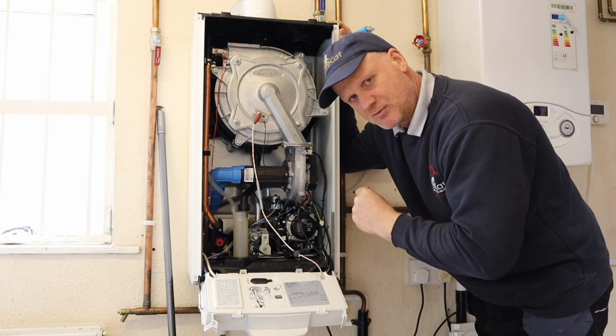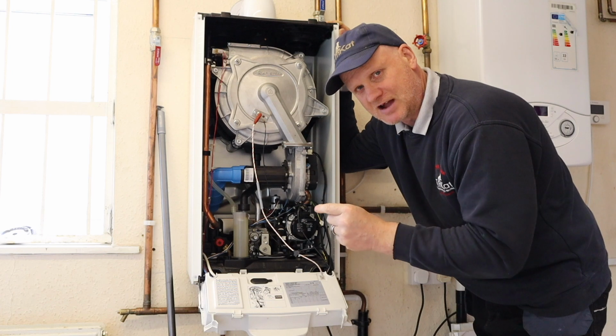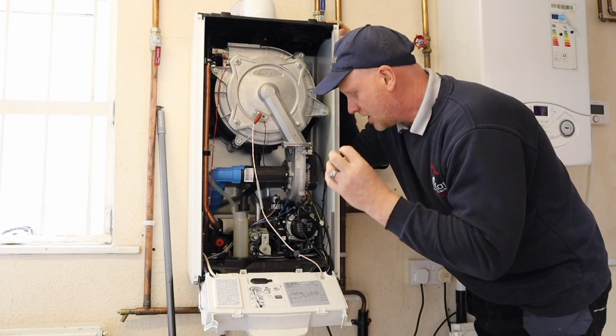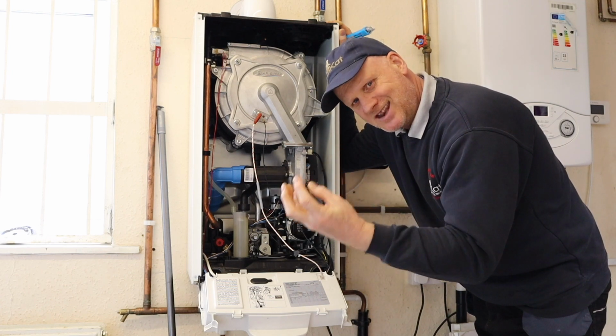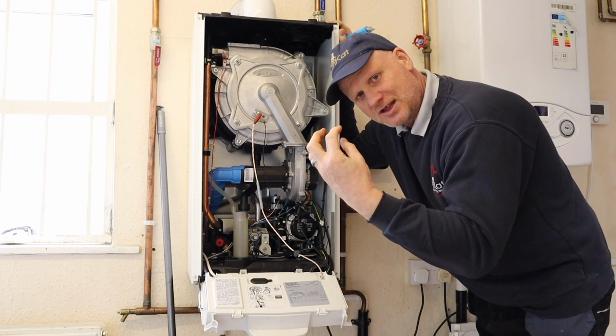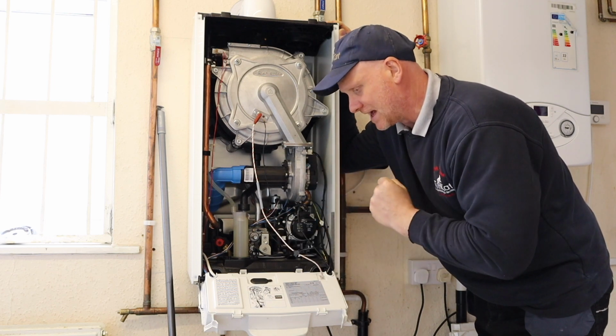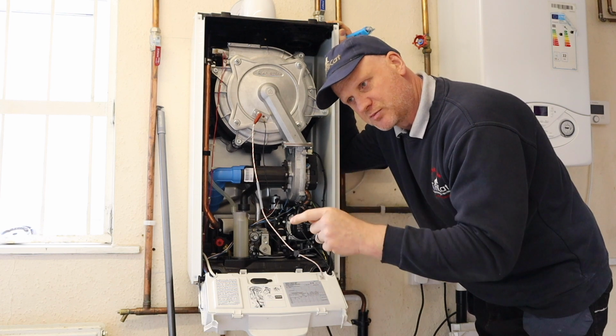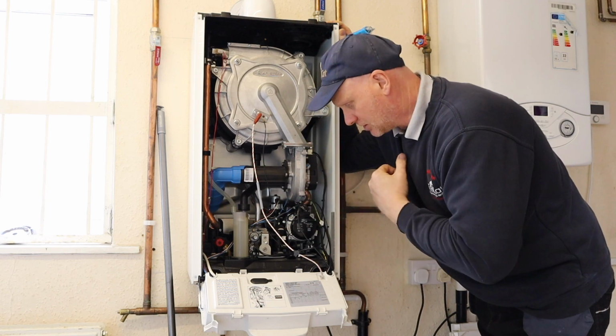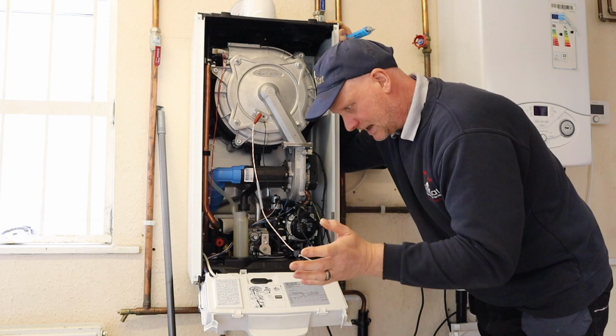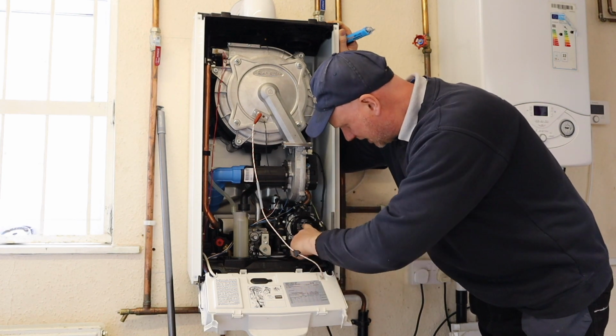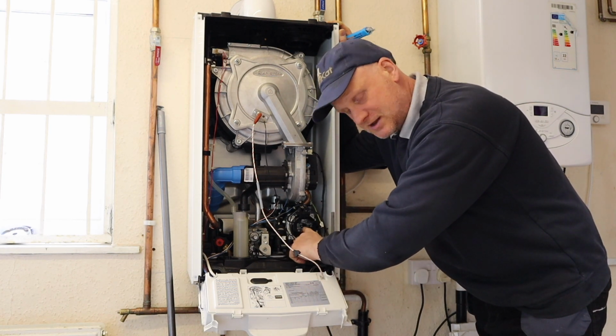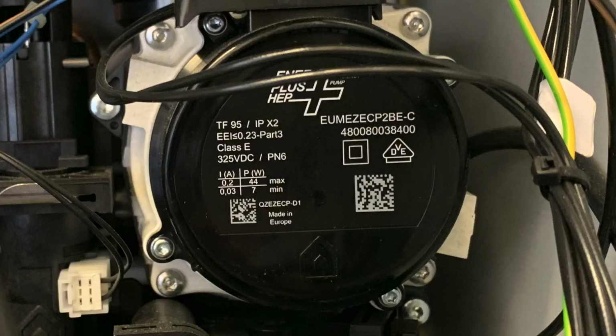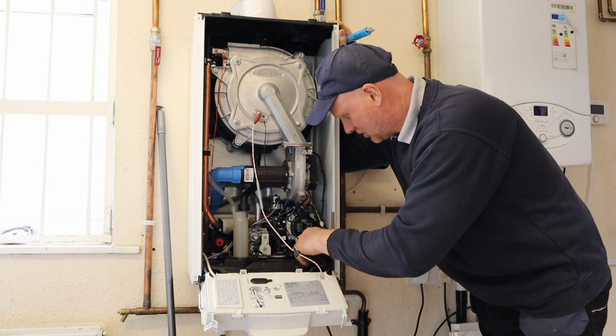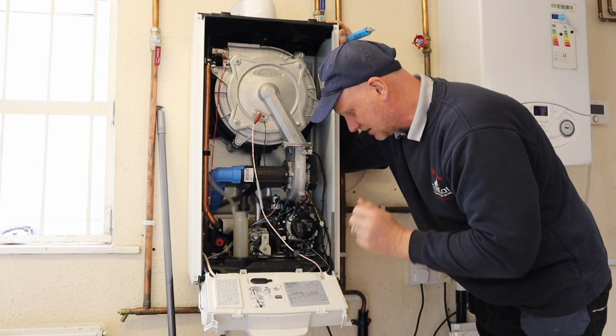Because if the return temperature comes back to a boiler greater than 55 degrees, it ain't going to condensate. Now also, it needs to reduce that energy as well it's using. So as it slows down, it's using less energy. But we can't reduce the speed without using the low voltage side on the boilers. Now, are they working? Can we tell they're working? This doesn't even have a screw hole in the centre here. You have to go through the sticker. So it's actually inside the sticker there. You could still put the screwdriver in and you can still do it.